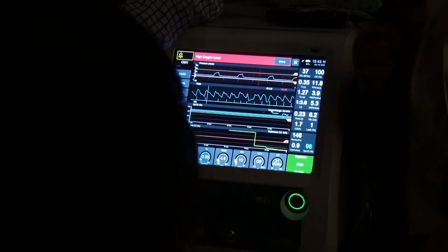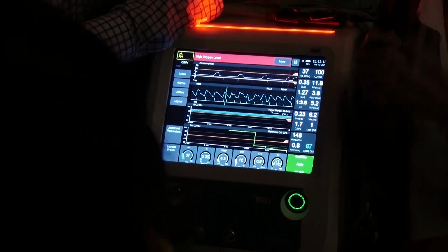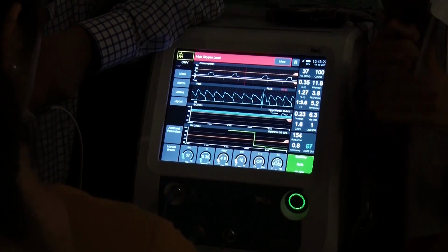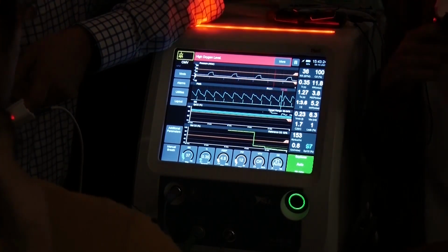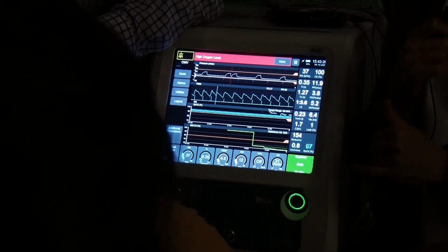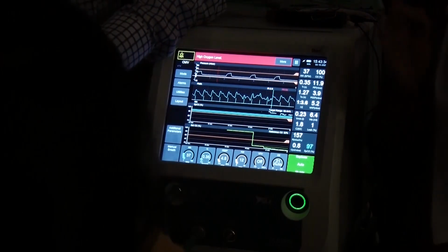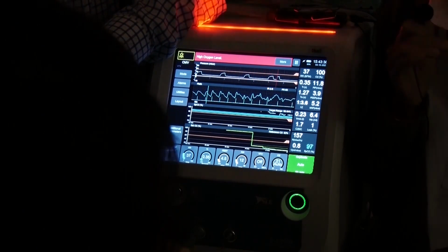When you have the nurses, they might go for hypoxemia, we go up, and then we see if they go back down to the same points as we started. If after a few adjustments they see that they keep going up, they might call you and say, I might have a problem. Here you won't see it, but you will see your reference O2, which is recalculated every 30 minutes, go up. And that tells you something changed.